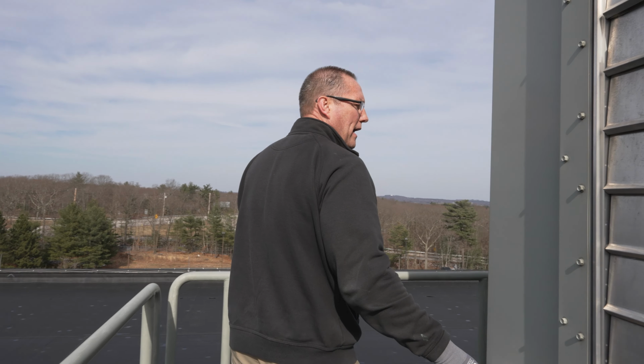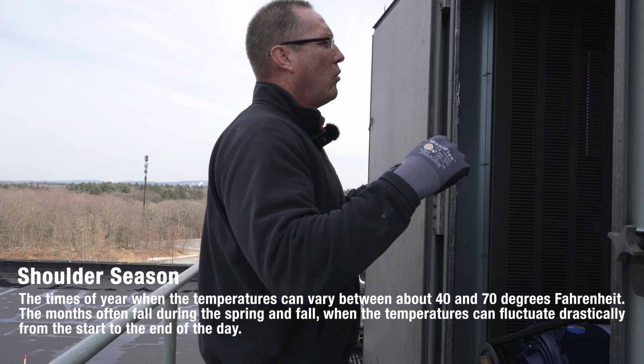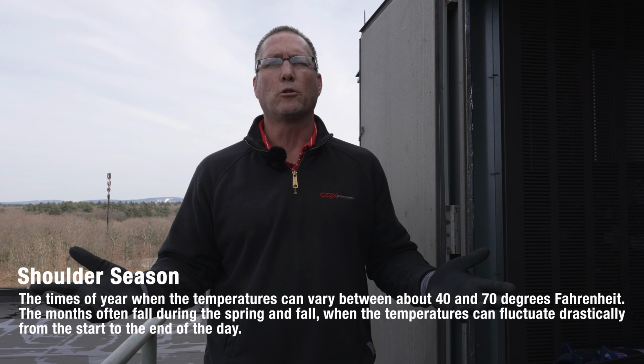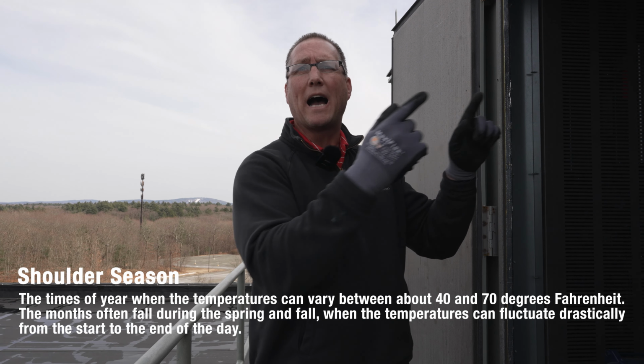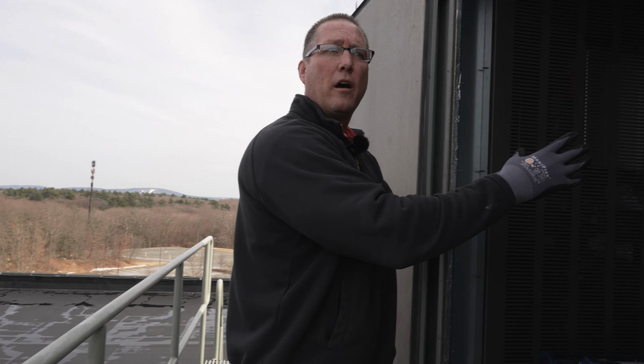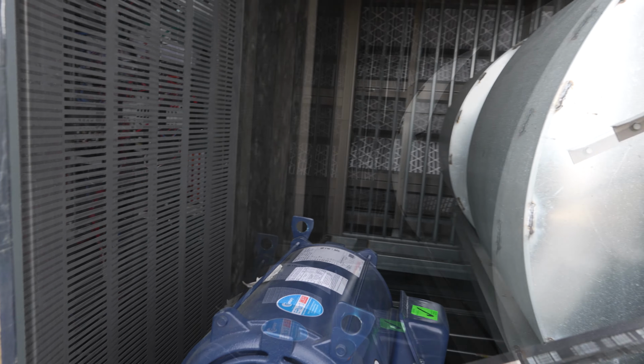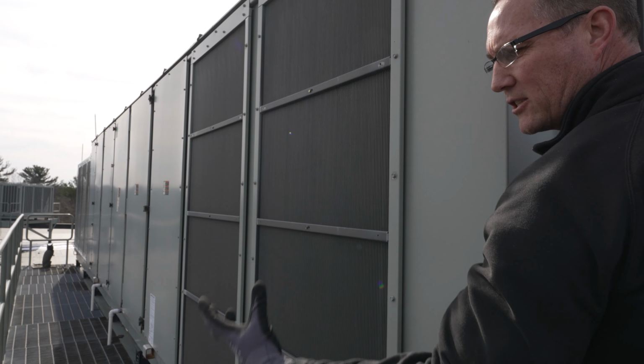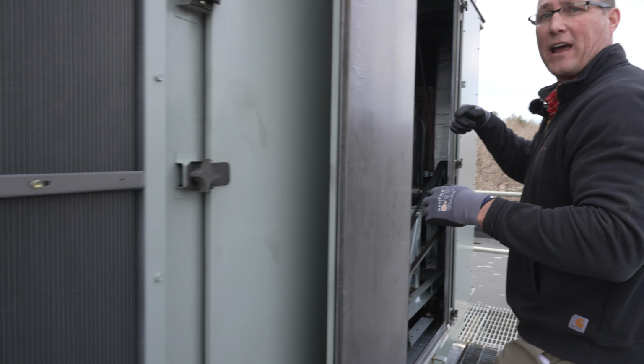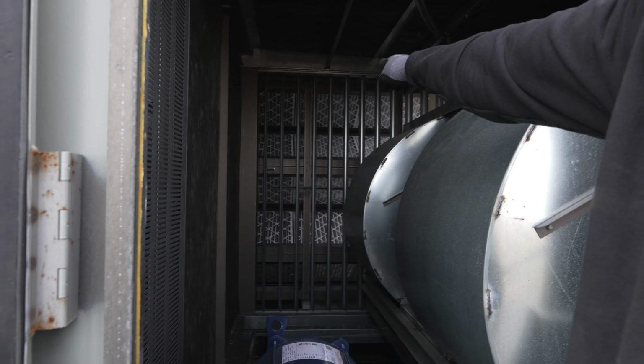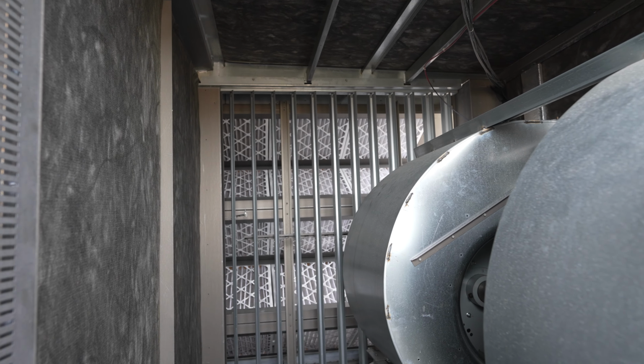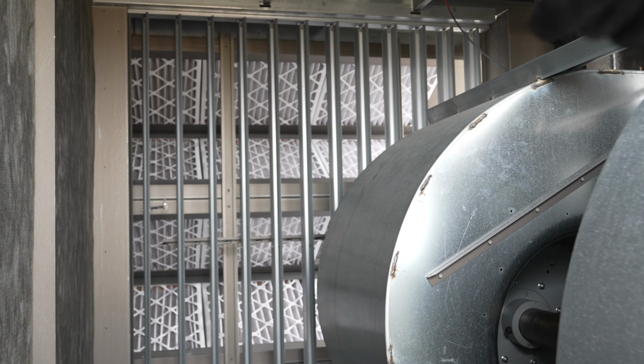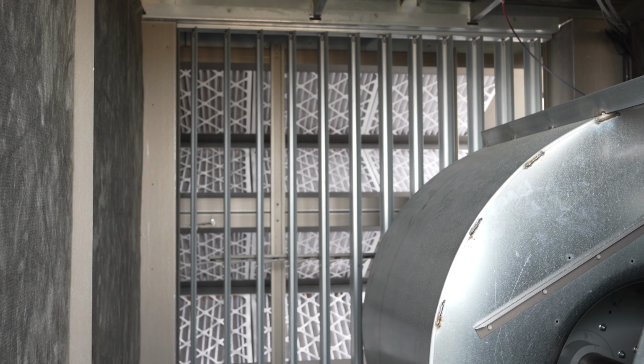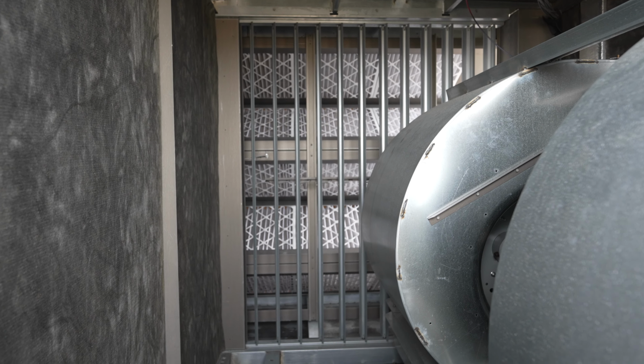So we're going to walk to the back side of the unit here. Right now we're in the shoulder season, meaning it's still cold outside. So sometimes we can use the outside air to condition the space, bringing cold air from the outside grills, which are right here. We're drawing air in. There are damper louvers allowing the air to be drawn in, and that supply fan that we were just looking at is drawing the air in and across the filters. So it's very important. You can see the dampers there, and a linkage off to the left in the middle there. We have to make sure all of that is intact so that we're bringing that air across those filters properly.